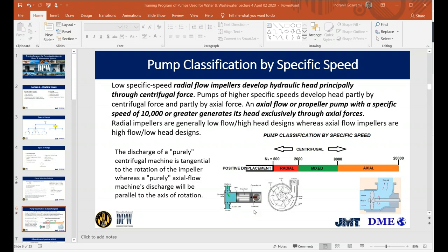Whereas in the second diagram, you can see a centrifugal pump casing where the flow is being spun circular, and the flow is essentially going out from the eye at the center to the outside part, the annular space in the outside part of the casing, and then the impellers are basically rotating it until they are discharged through the discharge piping on this side. So at that point, the flow direction is radial outwards into that outer part of the casing, and then the velocity of that fluid is essentially tangential, right? And it exits in a tangential direction.